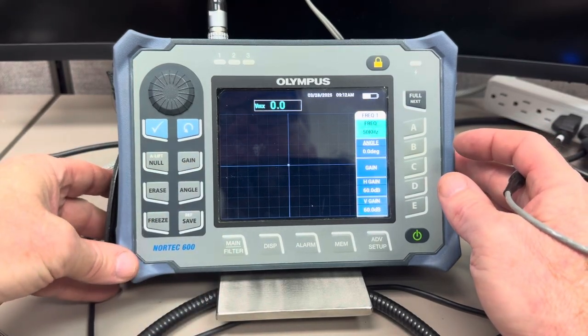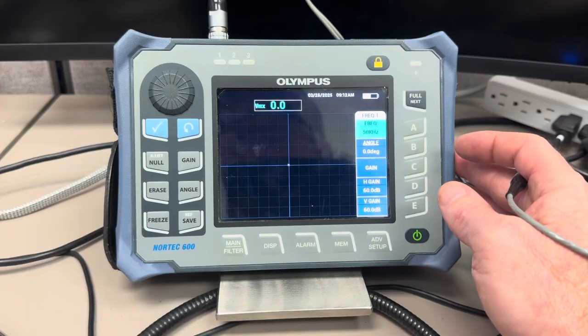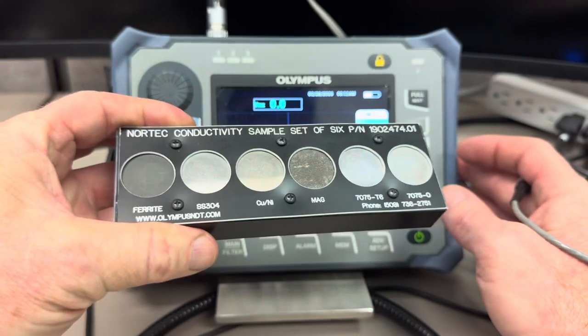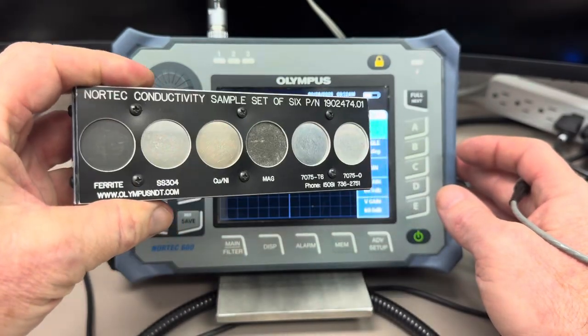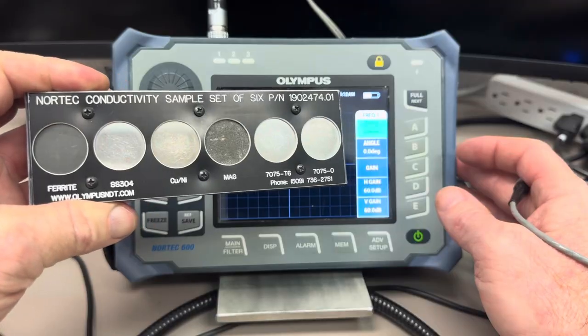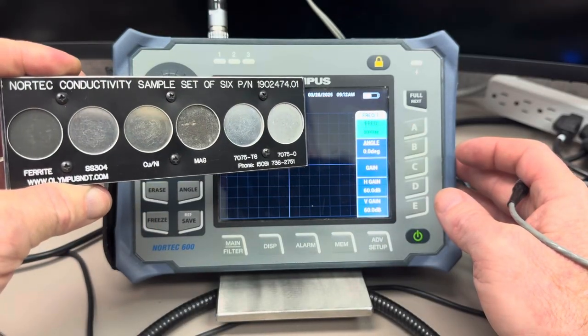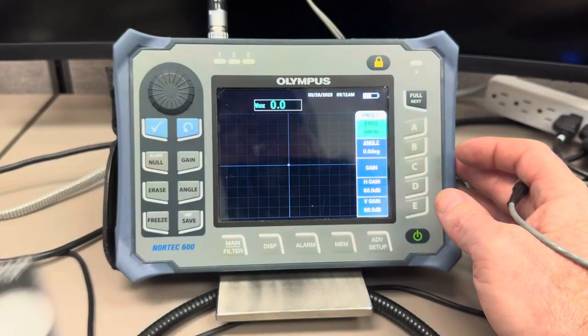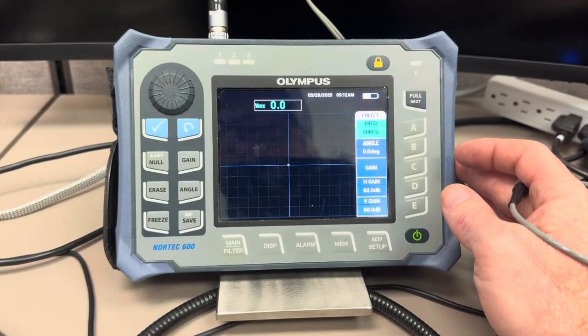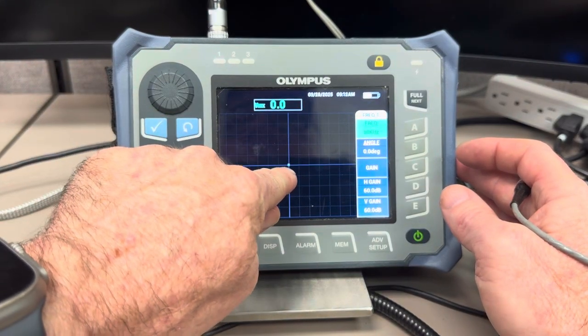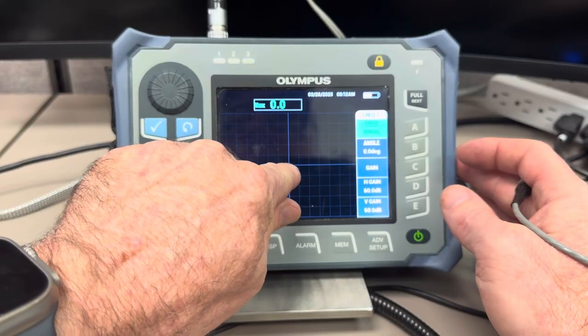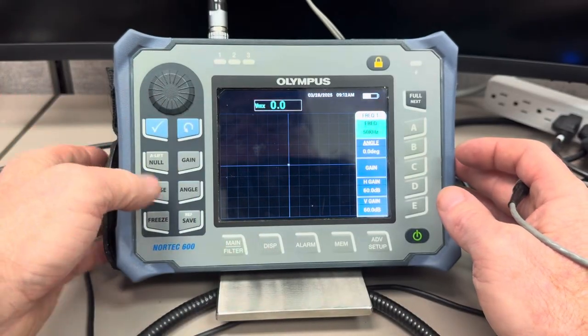Well when you're performing conductivity curves with sample blocks like this. This one is ferrite, 304 stainless, copper, nickel, magnesium, 7075 T6 aluminum, and 7075 0 aluminum. When using samples like that, normally what you do is you take your air operating point and you set it to the upper left hand portion of the screen.